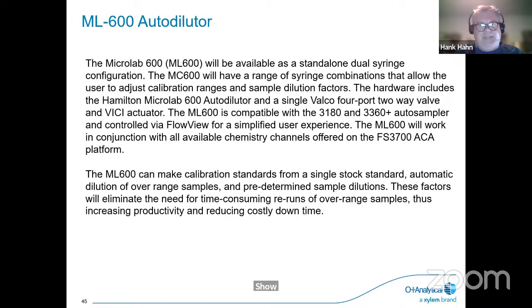So it's available as the add-on with the FS3700, built into the software. Our version 2.0 software supports this platform. So this will allow you to adjust calibration ranges and sample dilution factors. It includes the diluter. We use a Valco 4-port two-way valve with an actuator to help move that from the dilution over to the sampler and 3700. It'll work with both 3180 or 3360, controlled via the FlowView.